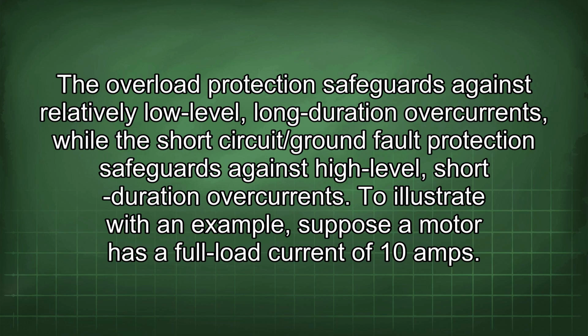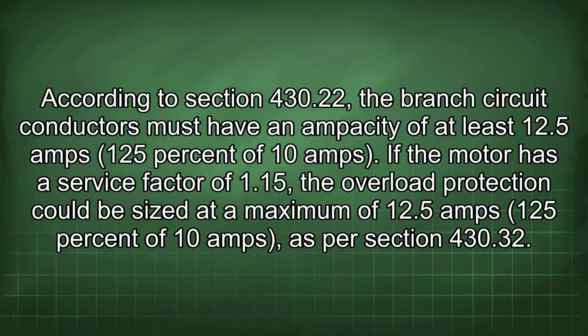To illustrate with an example, suppose a motor has a full load current of 10 amps. According to Section 430.22, the branch circuit conductors must have an ampacity of at least 12.5 amps, 125% of 10 amps. If the motor has a service factor of 1.15, the overload protection could be sized to a maximum of 12.5 amps, 125% of 10 amps, as per Section 430.32.